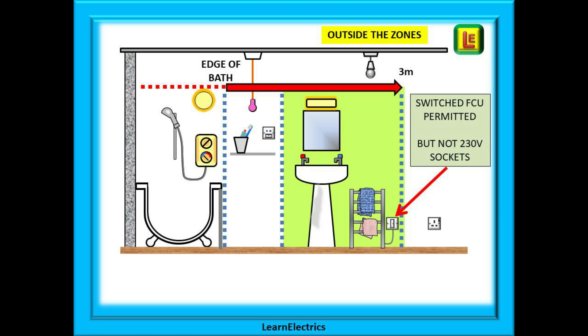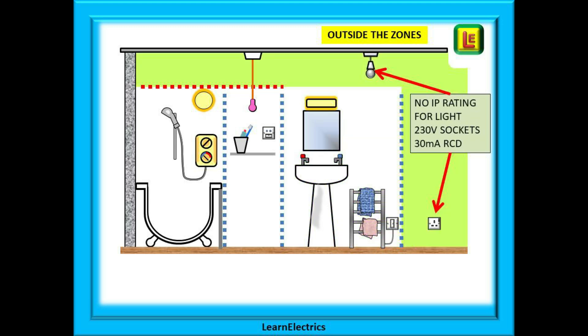230 volt sockets are not permitted in the area less than 3 metres from the edge of the bath. Once we move more than 3 metres from the edge of the bath, 230 volt sockets are permitted but must be 30 milliamps RCD protected. The ceiling light does not need to be IP rated, as all parts of it are outside zones 0, 1, or 2.